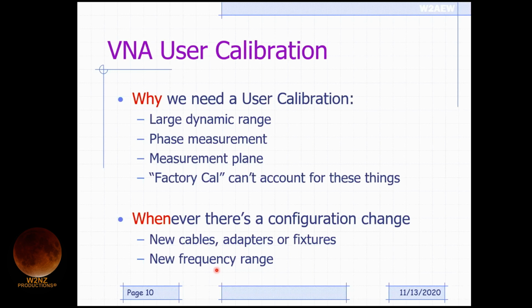Because when we run a calibration, it's measured at a specific number of points across a measurement span. If you change that frequency range, then the calibration points aren't necessarily going to be the same points that you're measuring. The VNAs will typically try to interpolate the results between those points, but it's always best to recalibrate. It only takes a minute to recalibrate whenever you make a frequency range change, okay?